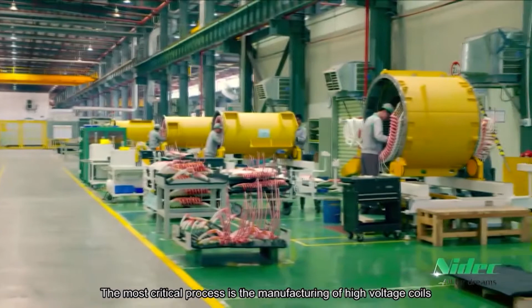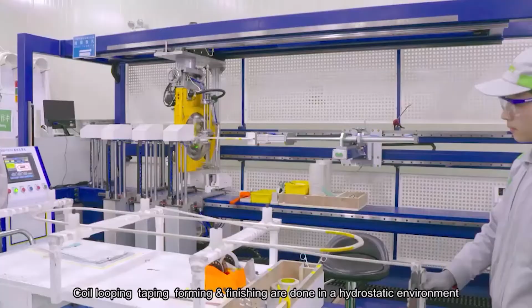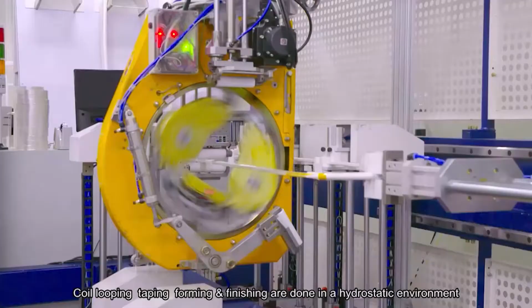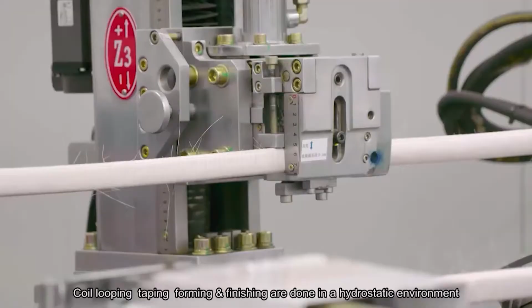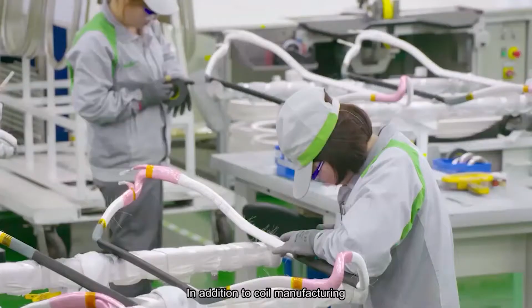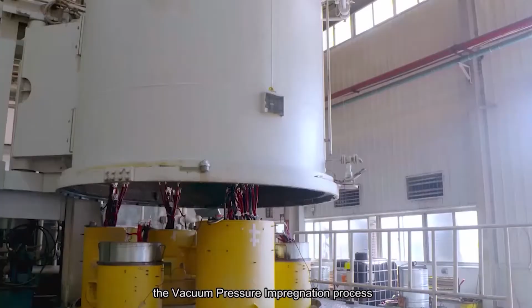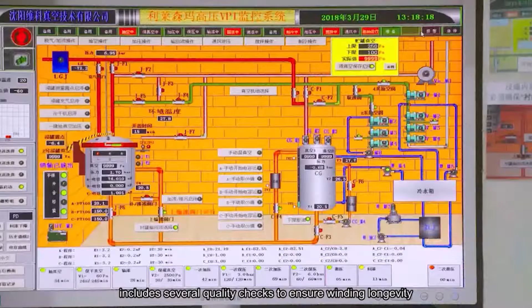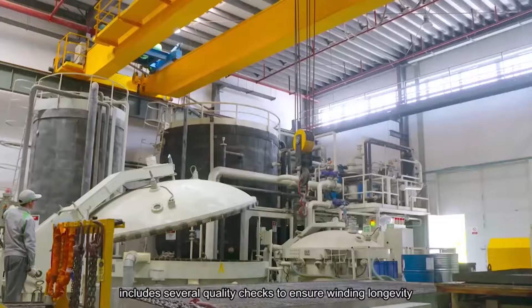The most critical process is the manufacturing of high voltage coils, which requires strict quality control. Coil looping, taping, forming and finishing are done in a hydrostatic environment. In addition to coil manufacturing, the vacuum pressure impregnation process includes several quality checks to ensure winding longevity.